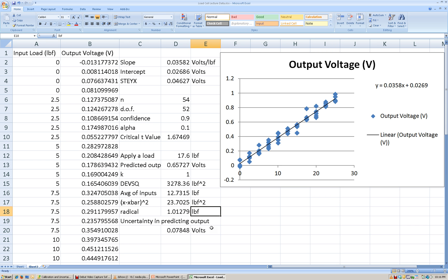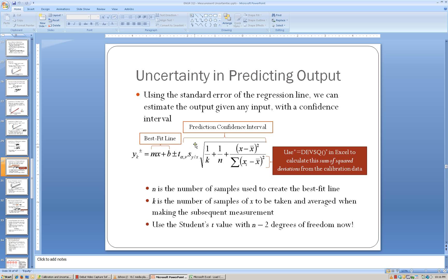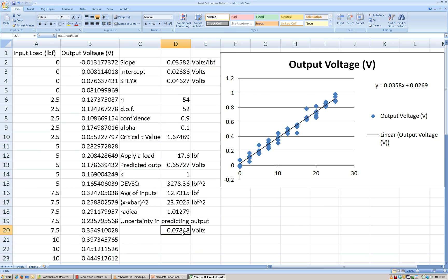That gives us the uncertainty in predicting the output based on the input. The product of the T-critical value, the standard uncertainty, and that radical term gives us our prediction confidence interval, which is going to be 0.0784 volts. So we can say that if we apply a load of 17.6 pounds to this transducer, we would expect to get an output of 0.657 volts with an uncertainty of 0.078 volts at a 90% confidence interval.